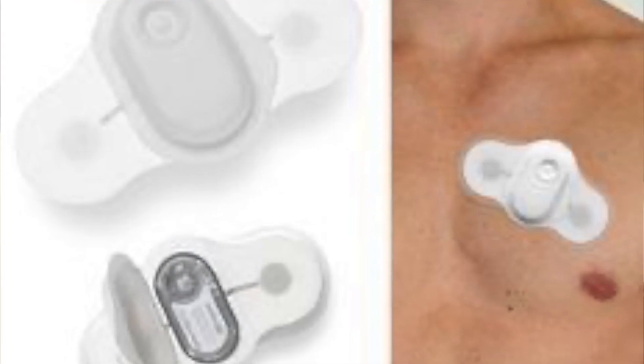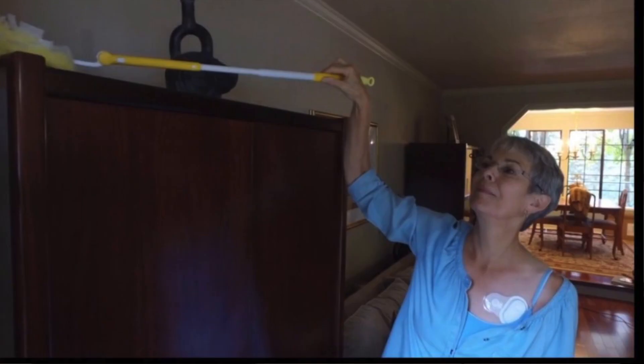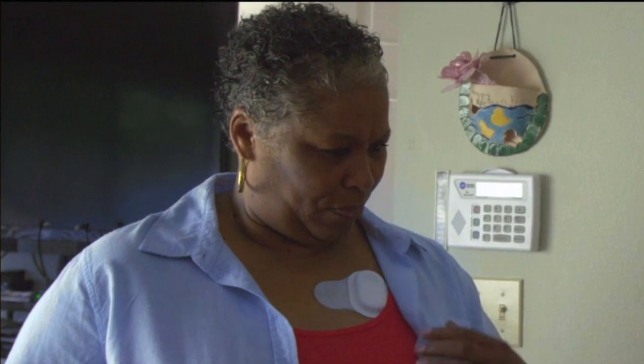The second type is ECG patches. These are wireless, water-resistant, self-adhesive patches that are easy to use and well-tolerated. They can stay on the skin from 5 up to 30 days and have a high accuracy and diagnostic yield that is even better than medical Holter monitoring devices. They are cost-effective and can detect clinically significant arrhythmia within the first week of monitoring. The only limitations are a relatively short battery life and sometimes the adhesive is not durable enough and the patch may fall off the chest.